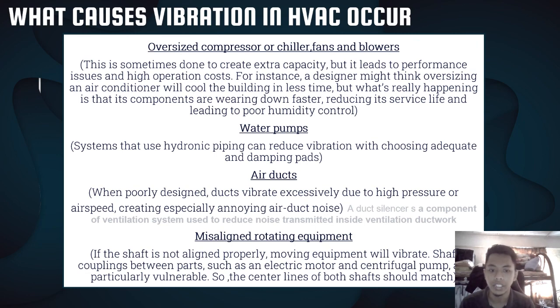And lastly is misaligned rotating equipment. If the shaft is not aligned properly, moving equipment will vibrate. A shaft is a coupling between parts, such as an electric motor and a centrifugal pump, so it is particularly vulnerable. So the center lines of both shafts should mesh together. You must find the center lines of both shafts, because when they are not aligned enough, this will vibrate the system.